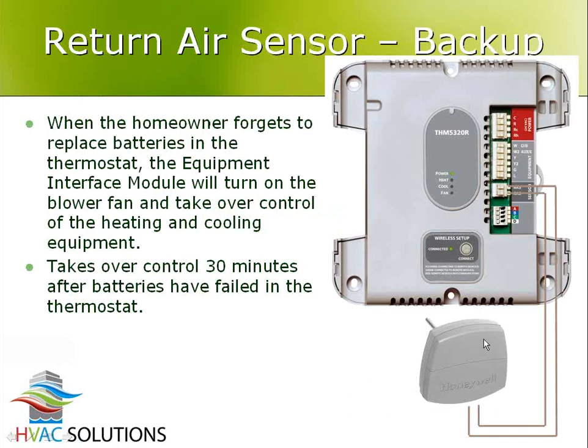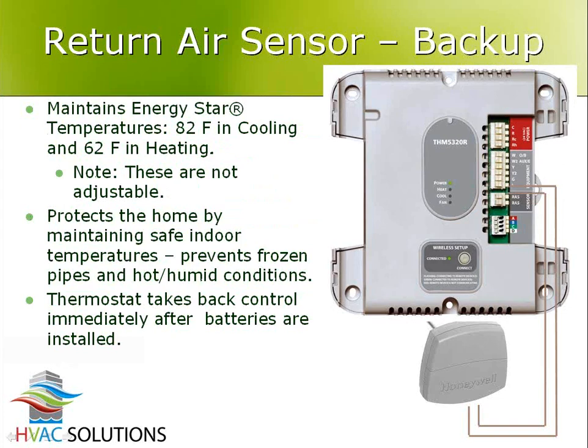Like I said, the return air temperature sensor is a backup. That's only there if after 30 minutes you can't talk to any of the stats for some reason. Then it'll say, okay, all the batteries must be dead, or somebody took them off the wall, or whatever happened. I'm going to go ahead and control the return air temperature because I don't have any other choice. And you don't really set the set points for that. It's basically in kind of a freeze protection mode. It puts in an automatic heating set point of 62 degrees just to make sure your house doesn't freeze. And what is happening here is we don't want it to be too high because we want it to be cold enough that people notice so they go fix their battery problem or whatever it is. But we don't want it to be so cold that stuff breaks, right? Pipes burst or anything like that.